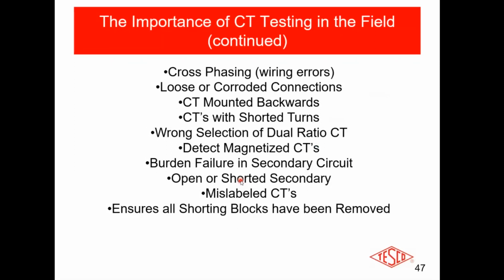How does that happen? It usually does happen when you put too much through it. A magnetized CT. One of the things you do when you do a burden test is you usually demagnetize those CTs at the end. You could get a burden failure. You could get an open or a shorted secondary. You could get a mislabeled CT. Just because it says it's 400 to 5 doesn't actually mean it's 400 to 5. While all the manufacturers are good, like all of us, we all have a bad day. We all make mistakes at times. And I used to think that was, well, how often could it happen? It actually happens more often than you would believe.